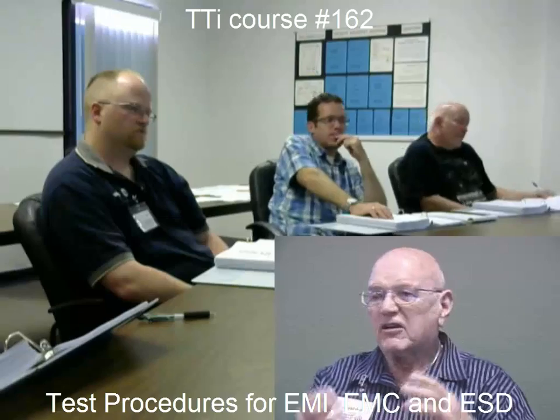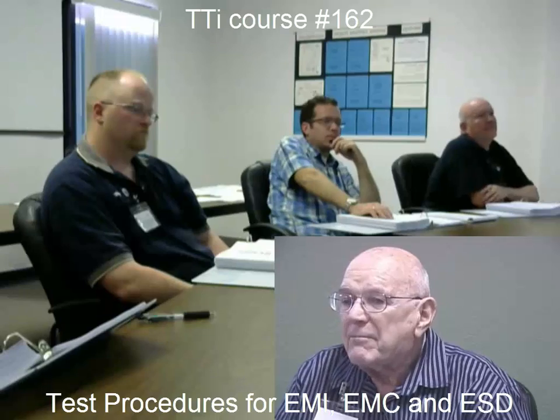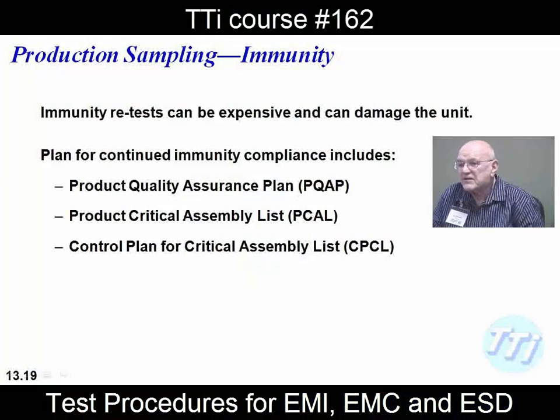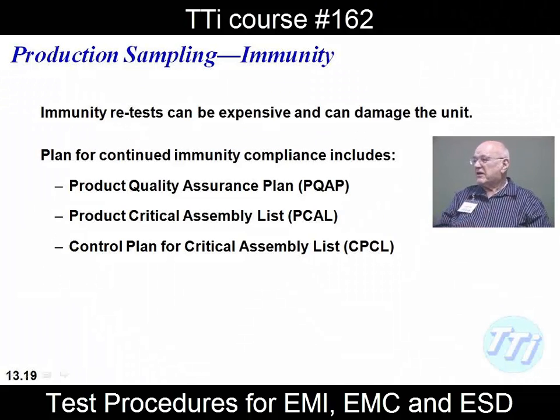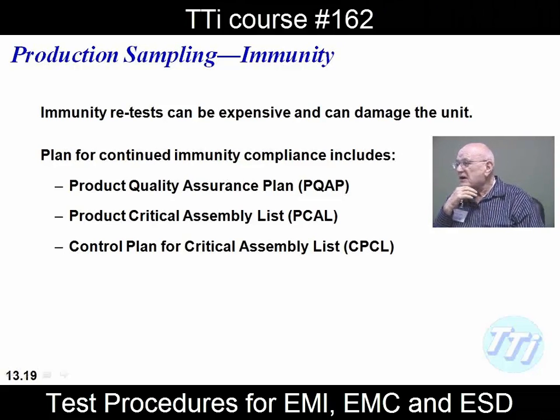They have a rate that they book our lab time at. Yes, I understand. But what I'm getting at is that when you actually go out to be tested for real, not the pre-compliance, but the real thing, the test may cost $50,000. And when we talked about pre-compliance, I showed you the video on that, that you go in and you can make a change and go back another $50,000. You go back and another $50,000. And that's what happened in your case, wasn't it, Tom, as far as your company was concerned? So they said maybe we should be doing some pre-compliance because of this.